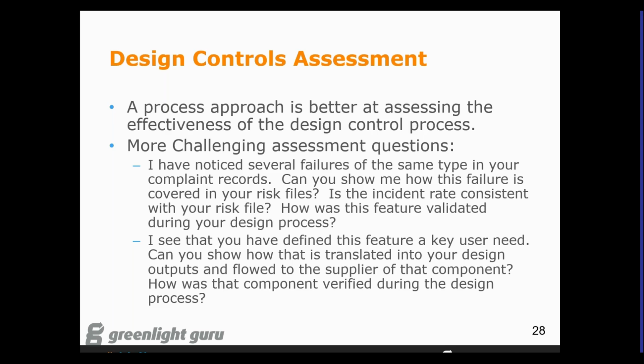Some of these questions would be: I've noticed several failures of the same type in your complaint records. Show me how this failure is covered in your risk files. Is the incident rate consistent with what you have documented in your risk file? And how was this feature validated during your design process? And then you scurry around. You call up your subject matter experts, the guy that wrote the FMEA, and go, where's this covered? And you rummage around and you try to find the best fit.